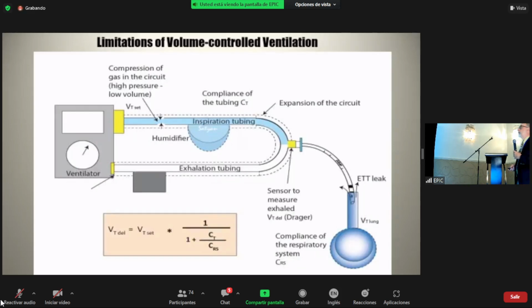So the adult kind of volume controlled ventilation. There are two ways of delivering or regulating tidal volume. One is what PICU and adult ICUs do, and what some of our ventilators like the Servo have, a volume controlled mode. In these volume controlled modes, you have a ventilator that generates the tidal volume, measures it, regulates it here at the ventilator end of the circuit, okay? And a significant portion of that tidal volume dissipates to compression of gas in the circuit, which can be compensated. And there's this compliance compensation feature that works pretty well, unless there is a leak around the endotracheal tube. And when there's a leak here, that compliance compensation begins to break down, and there is no compensation for the leak around the endotracheal tube.